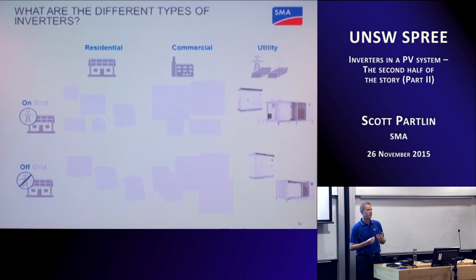They're potentially the same as, or they can be treated the same as, your typical coal-fired power station or a large wind farm, gas peaking turbines. So they need to fulfill different sorts of roles. And similarly with storage, but one of the common things, whether it's on-grid or off-grid, is that essentially every inverter has within it a capability to be either an on-grid inverter or an off-grid inverter. And the only difference is whether that inverter is synchronizing its output to a grid or whether the device itself is being relied upon to actually form the grid, to form the AC sine wave.